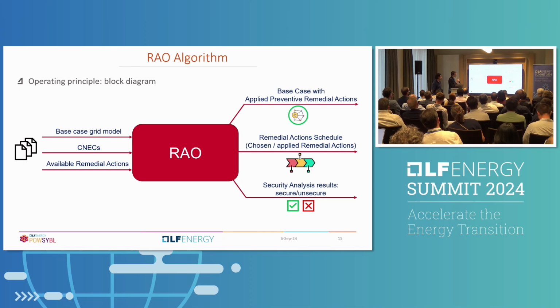A RAO, whether it's capacity calculation or ROSC, is going to work with a base case grid model, so the famous common grid model usually, with CNECs. If you like acronyms, CNEC means contingency and critical network element and contingency. So it's a combination of an asset element, so a line or a transformer, and a contingency, which means that you are going to check that there is no violation of the thermal limit on this network element after the given contingency.